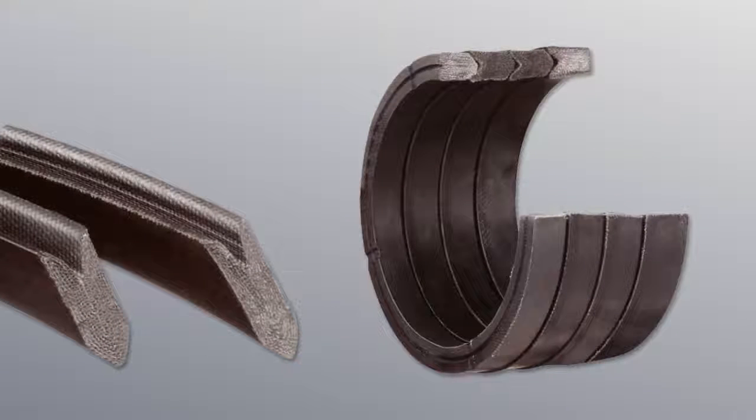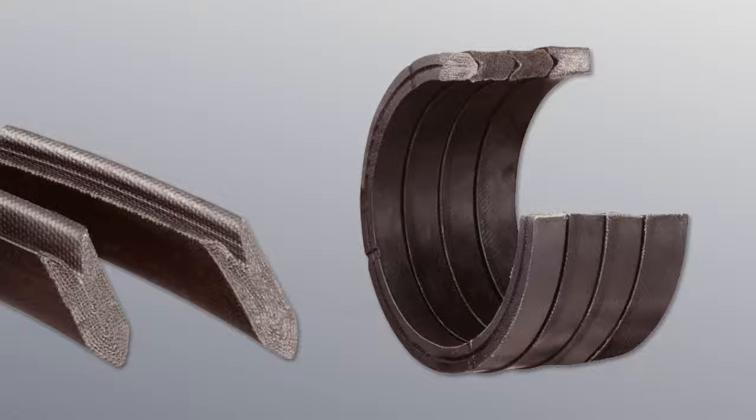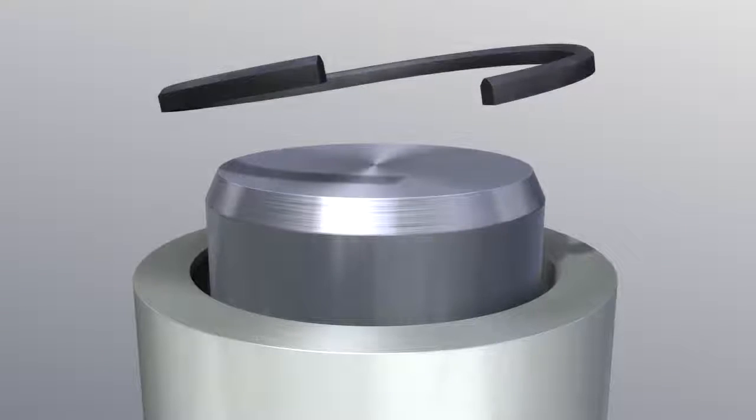V sets and lip packings with a diameter of 400 mm and larger are supplied in open condition and are oversize in length. The seal sets must be cut to the specified size just before installation. Do this in the order the seals fit in the gland.